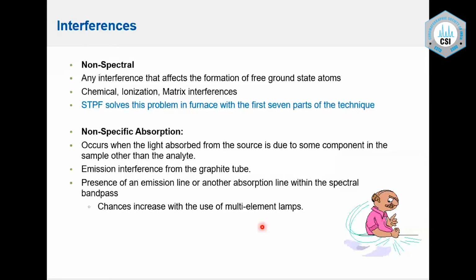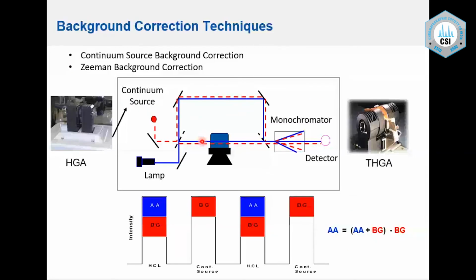So in a graphite furnace, normally we don't face this kind of interference because of the STPF concept. Non-specific absorbance: these are interferences you normally get because of some unwanted components available in your sample. This unwanted material absorbs the light from the lamp and you get some extra values.